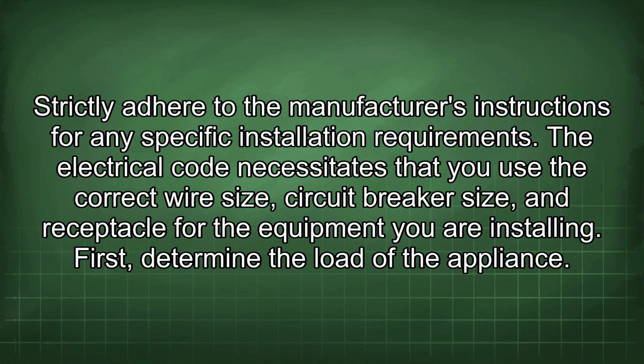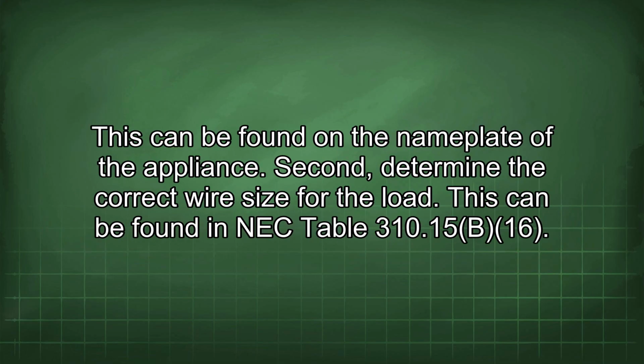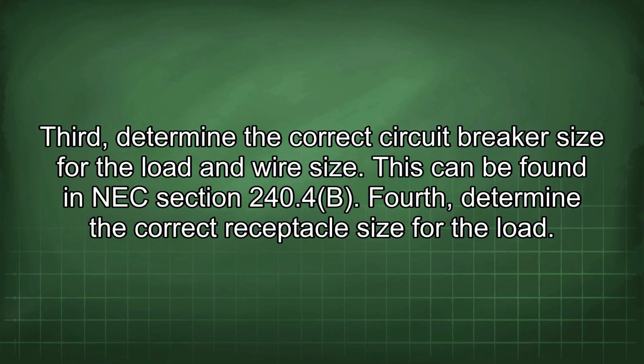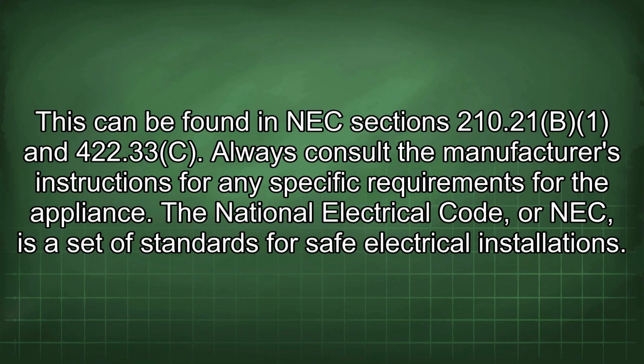The electrical code necessitates that you use the correct wire size, circuit breaker size, and receptacle for the equipment you are installing. First, determine the load of the appliance. This can be found on the nameplate of the appliance. Second, determine the correct wire size for the load. This can be found in NEC table 310.15(B)(16). Third, determine the correct circuit breaker size for the load and wire size. This can be found in NEC section 240.4(B). Fourth, determine the correct receptacle size for the load. This can be found in NEC sections 210.21(B)(1) and 422.33(C). Always consult the manufacturer's instructions for any specific requirements for the appliance.